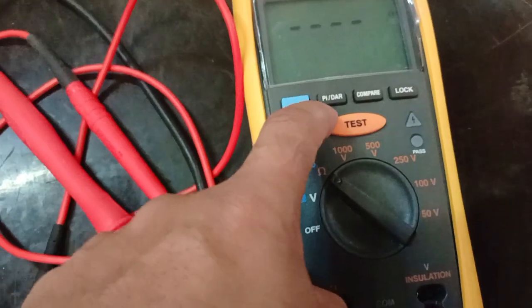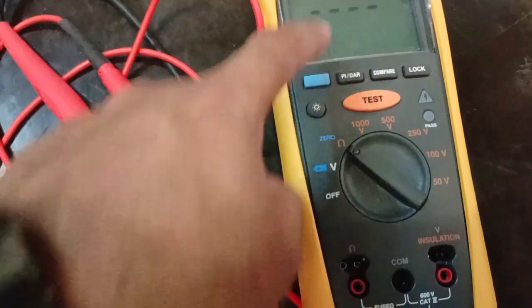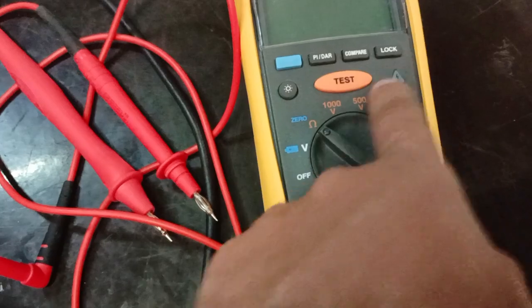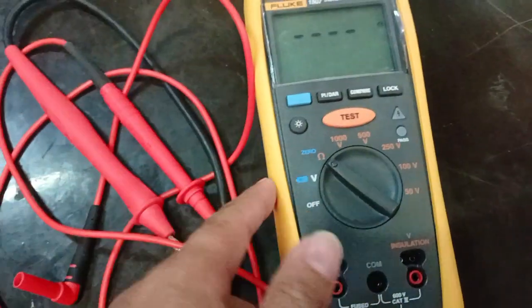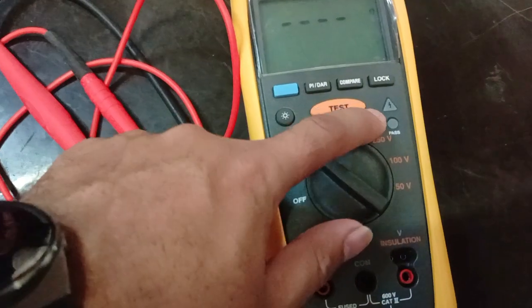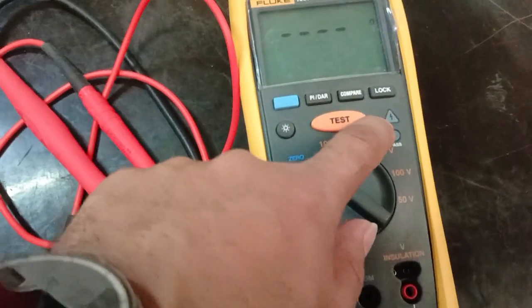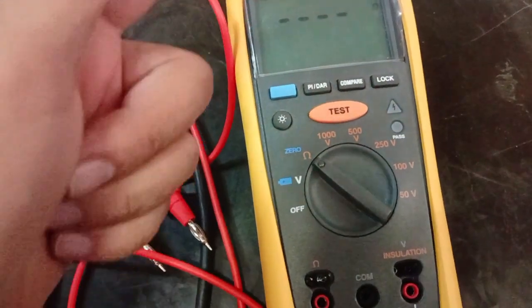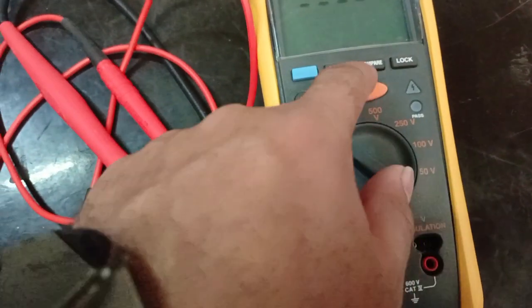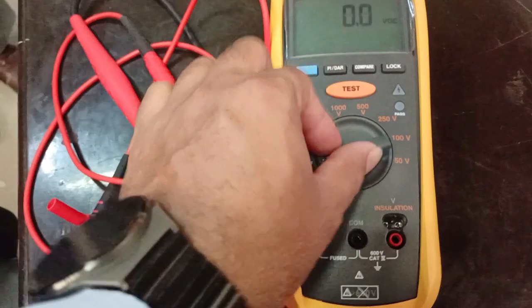This PI/DAR function is for checking the winding of transformers and motors. This button is for the display light. The lock button means while testing, if you want to hold for one or two minutes, you press lock and then test — it will continuously inject the voltage. Otherwise, you hold the test button to apply voltage. This LED indicates that output voltage is going out, and this LED light shows pass or fail based on the limit set in the compare button.